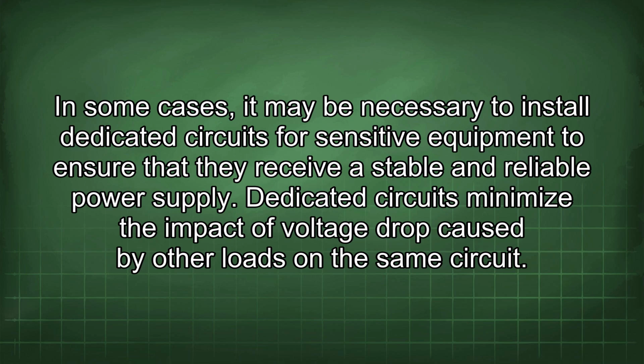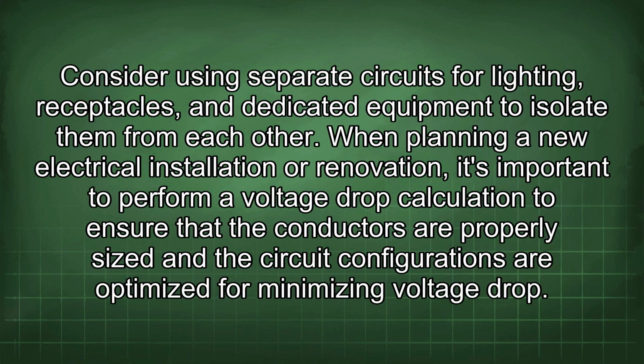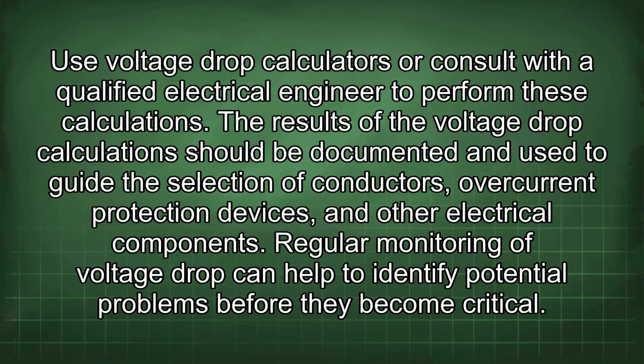Dedicated circuits minimize the impact of voltage drop caused by other loads on the same circuit. Consider using separate circuits for lighting, receptacles, and dedicated equipment to isolate them from each other. When planning a new electrical installation or renovation, it's important to perform a voltage drop calculation to ensure that the conductors are properly sized and the circuit configurations are optimized for minimizing voltage drop. Use voltage drop calculators or consult with a qualified electrical engineer to perform these calculations. The results of the voltage drop calculation should be documented and used to guide the selection of conductors, overcurrent protection devices, and other electrical components.